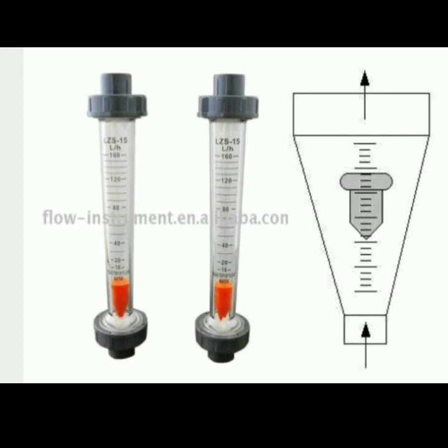The greater the rate of flow, the higher the plummet rises in the tube. And in this rotameter the pressure drop is constant or nearly constant. During fluid flow the area of the annular space between the plummet and the tube varies. Therefore the head loss across the annulus is equal to the weight of the plummet.